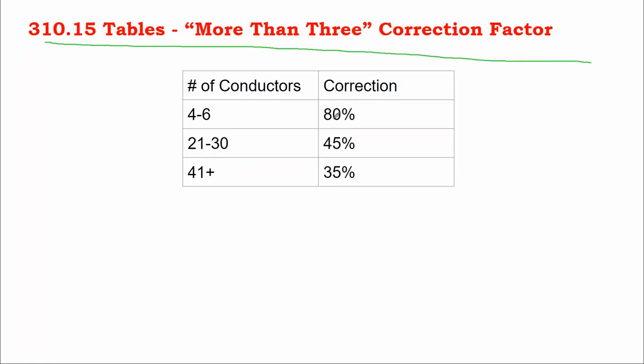Actually, not a huge deal. The reason why some of these tables are incomplete is I can't give you a complete copy of the National Electric Code for you just to print out and have as a handout, unfortunately. So there's missing data inside of here, but what we're trying to do is illustrate the point. The more conductors you have bundled together, the greater the derate.